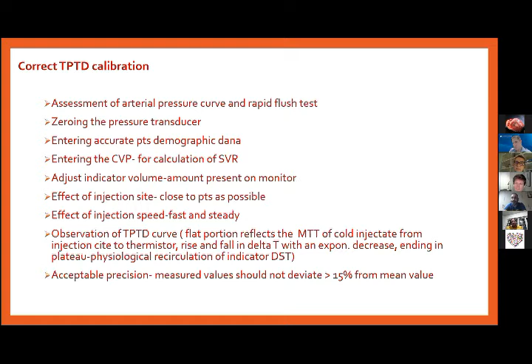What is acceptable precision in terms of PiCCO? If we are taking 3 measurements, the measured values should not deviate more than 15% from the mean value, so that we can say it is adequately calibrated. What we should also take into account, now that we know we have done something properly in a mechanical way, is that we have to think about the patient, the diagnosis, and the pathophysiological issues, and take that into account with the transpulmonary thermodilution data that can be provided.